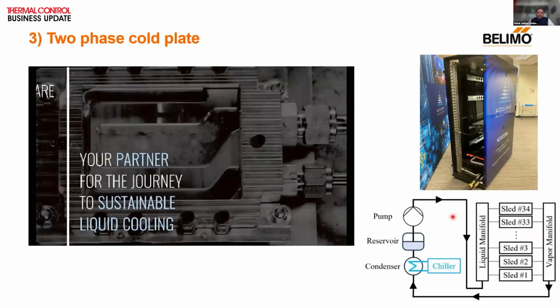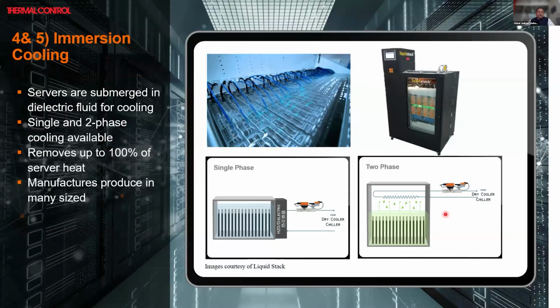Third is the two-phase cold plate. I think we can speak about this here. So here you have immersion cooling. These are the server racks which are inserted into dielectric media, and then there are two ways: single phase cooling, wherein again this control valve plays an important role to modulate the flow, and two phase, where we again have this control valve which plays an important role to modulate the flow. So that's all about the technologies and where Belimo has its application and the distinct features that we can provide.